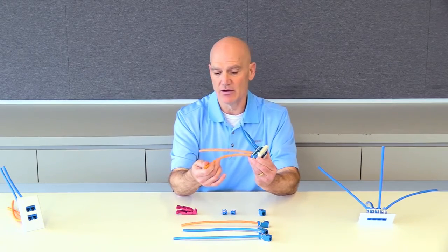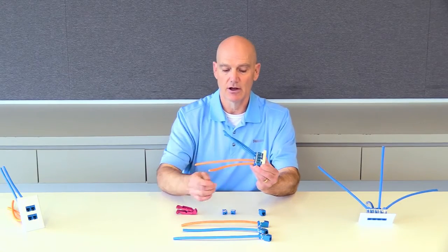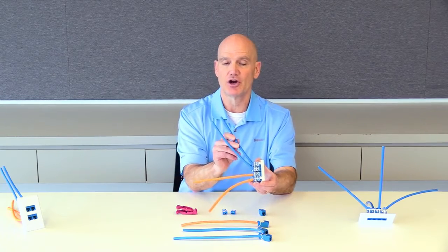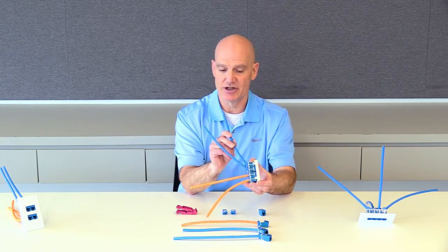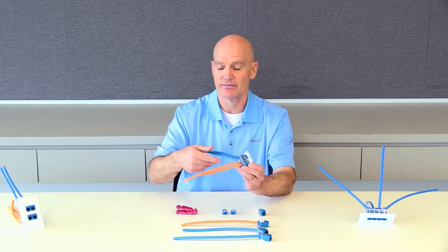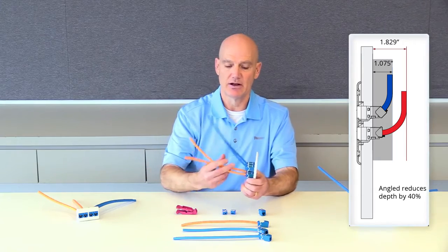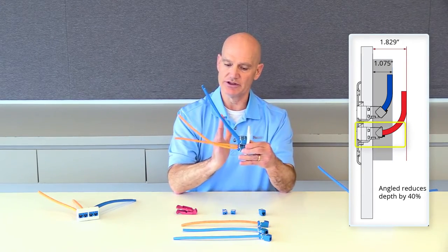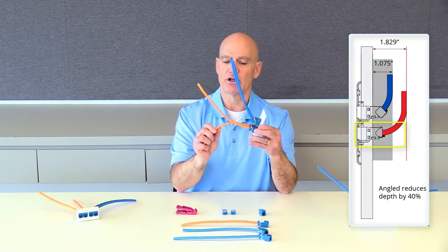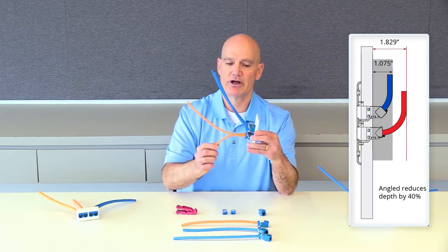In the straightaway orientation, the bend radius becomes exceeded, whereas in the left-right orientation, we actually start the cable in the bend position, and this allows us to not exceed that bend radius. Conversely, when we come out of a faceplate, and let's say the wall is only 2 inches deep, the straightaway does not allow for the bend radius. It will exceed that bend radius.